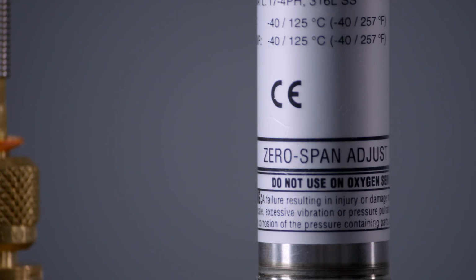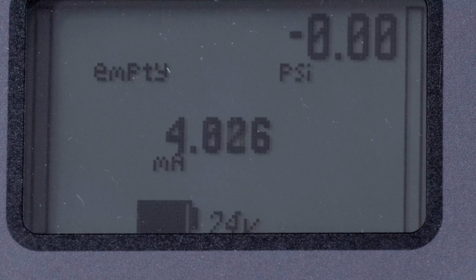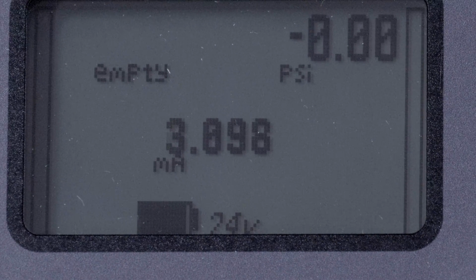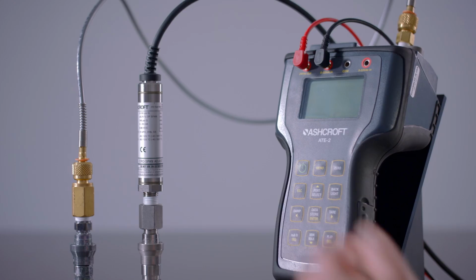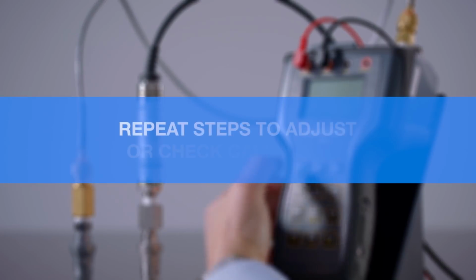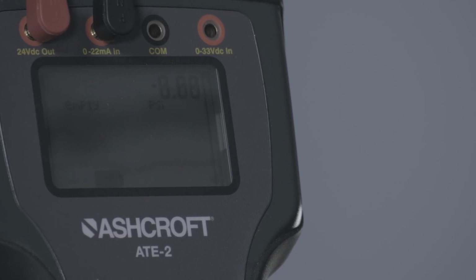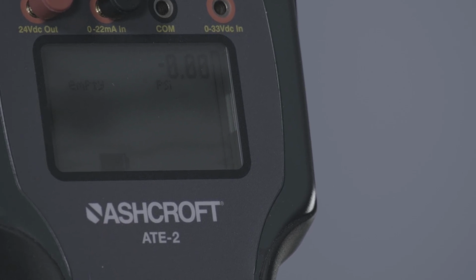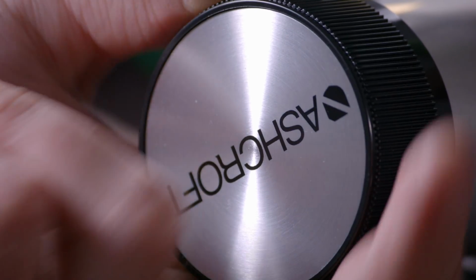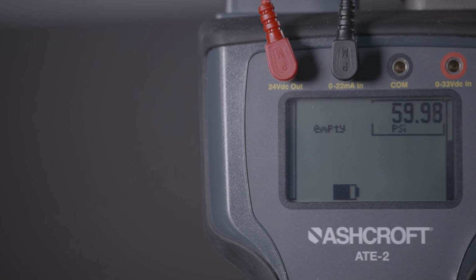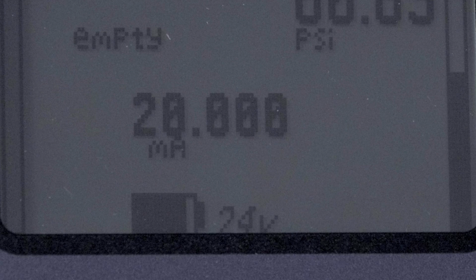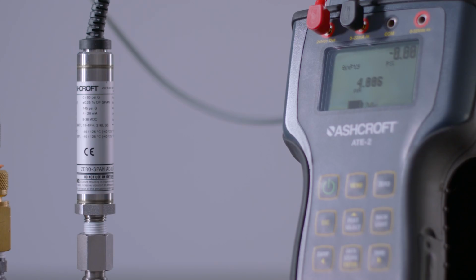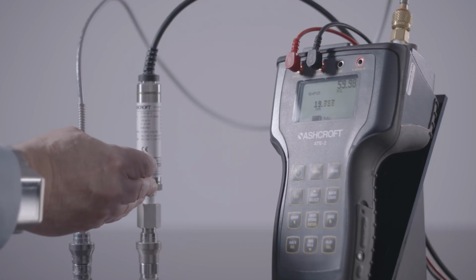This will be signaled by the output of the transducer, driving to over range, under range, and back to the normally calibrated output. The E2G is now calibrated, and you can repeat the steps shown previously to check the offset and span values. To verify it has been properly calibrated, raise the pressure from 0 to full span. The span is at 20 milliamps. Now lower the pressure to 0 and the offset is 4 milliamps. If you need to make adjustments, re-enter calibration mode and repeat the adjustment steps as shown.